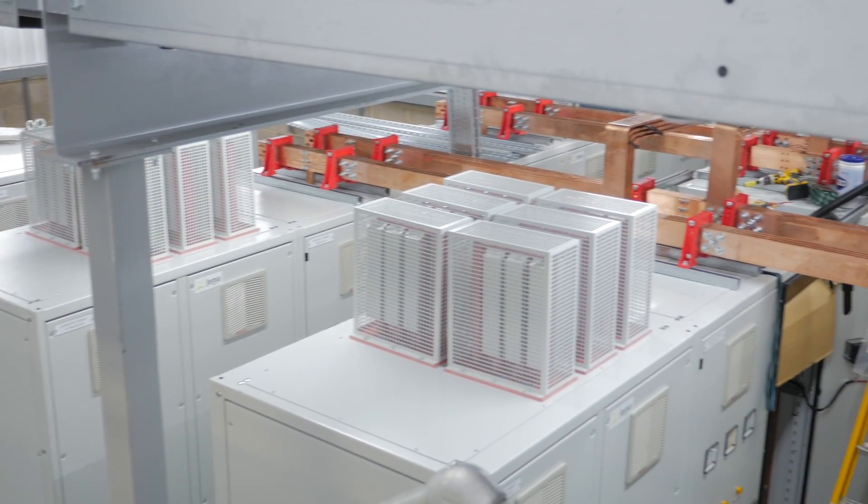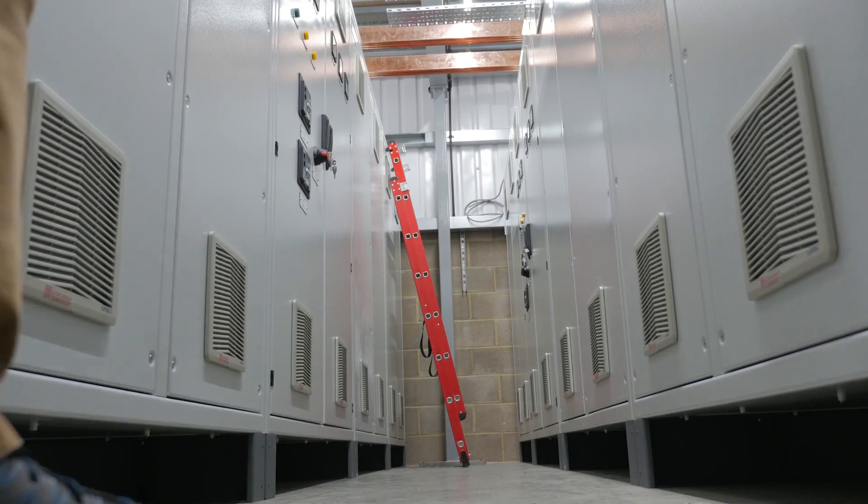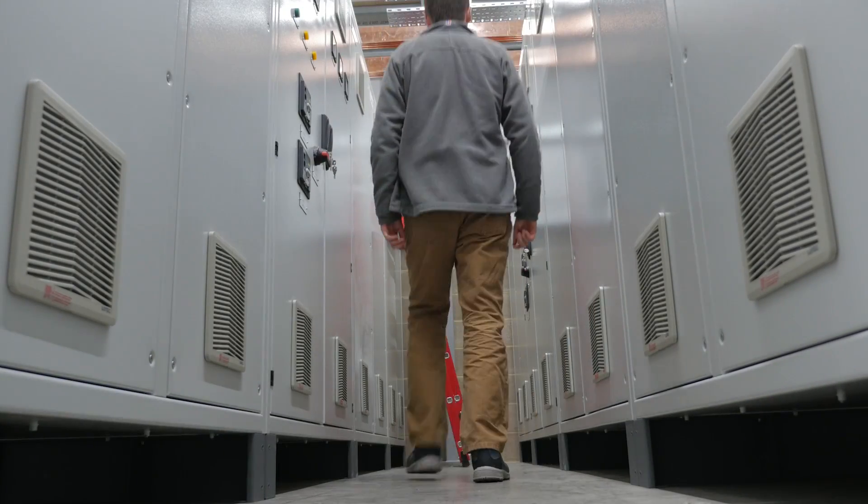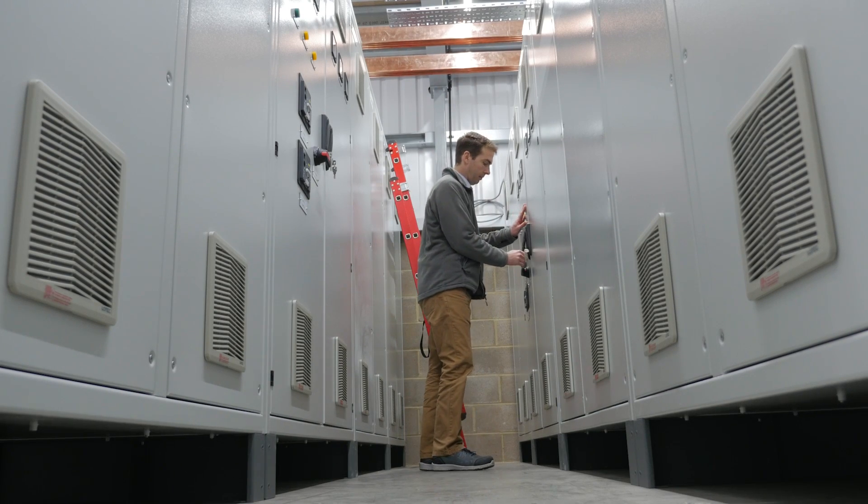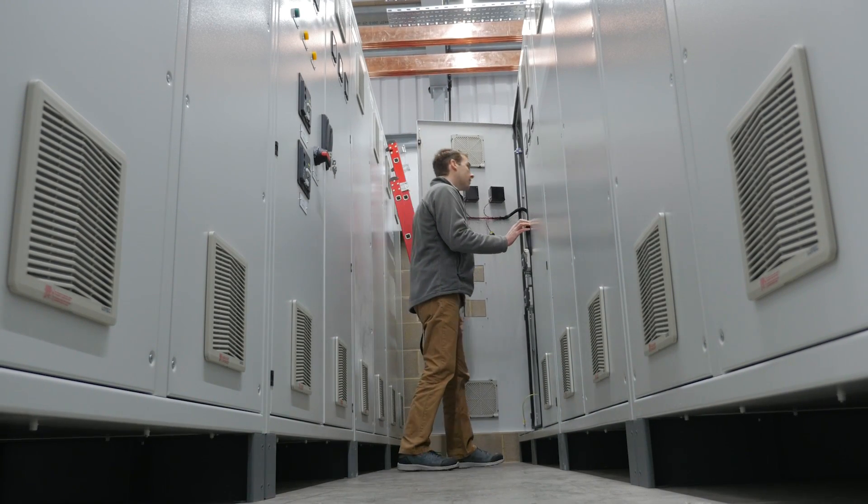we're finished and all the power supplies are delivered, we'll have basically two levels this size filled with cabinets filled with capacitors. And so we've had to buy in a diesel generator set to provide us enough power to charge up the power supplies. The idea is they need to be charged up within about 20 minutes or so.